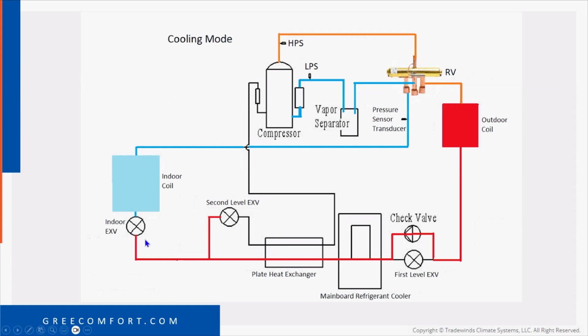So then our liquid refrigerant goes to our indoor EEV, or EXV, whatever you want to call it. We got away from that with the 410A. With 410A, this was a TXV. Now it's an indoor EXV. It meters refrigerant into our indoor coil, where we're flashing off and absorbing heat. Our cool suction gas comes back, goes through our reversing valve into our permanent suction port right here, through what they call a vapor separator. It's the same thing as an accumulator. Then out of the accumulator, you've got the low pressure switch, and into another accumulator that's attached to the compressor. So that's, in a nutshell, your cooling mode operation.